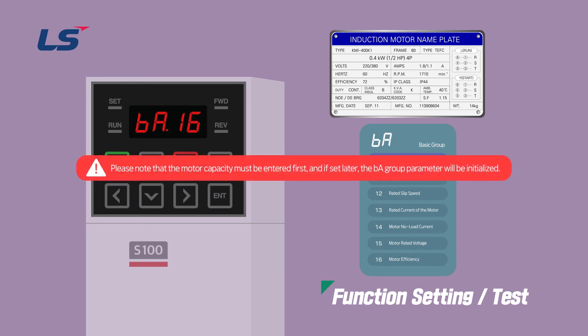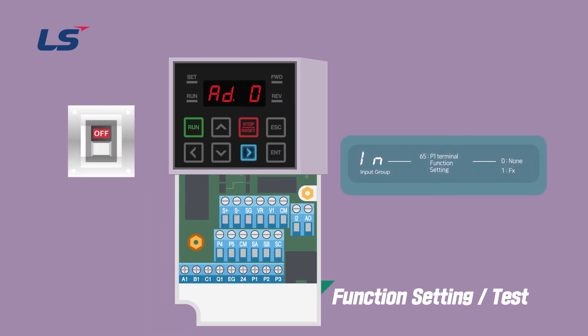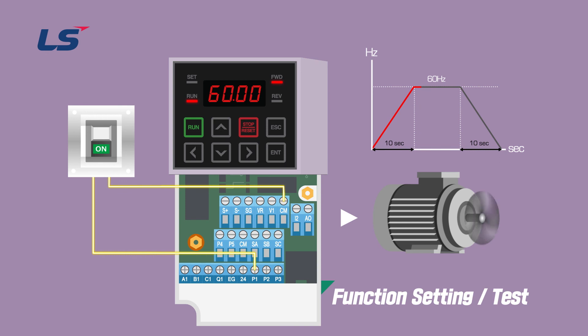As a precaution, the motor capacity must be entered first. If set later, the BA group parameter is initialized, so please be careful. To set the operation command in the terminal block, set the P1 terminal function setting, which is number 65 of input group, to 1, which is the forward operation FX. Since P1 is set as a forward contact, wire the switch to P1 and CM. If you switch ON, you can see that the target frequency goes up to 60 Hz for 10 seconds of acceleration time. When the switch is turned OFF, it can be confirmed that deceleration stops for 10 seconds, which is the deceleration time.